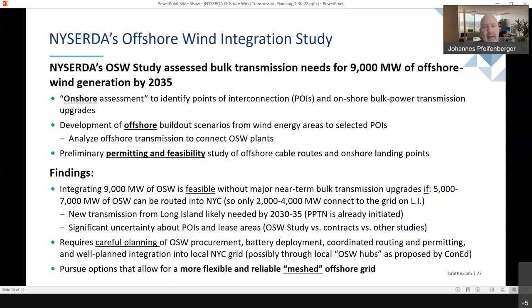The study found that if you carefully select the interconnection points by choosing the most robust and reachable points on the onshore grid, integrating 9,000 megawatts into the New York grid is feasible without major near-term bulk transmission upgrades beyond what the state has already planned. It would, however, require that 5,000 to 7,000 megawatts of that 9,000 megawatts be routed into New York City. So only about 2,000 to 4,000 megawatts would need to connect to Long Island.